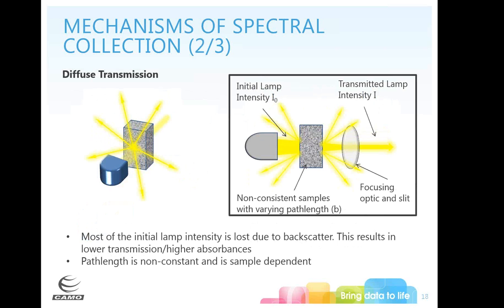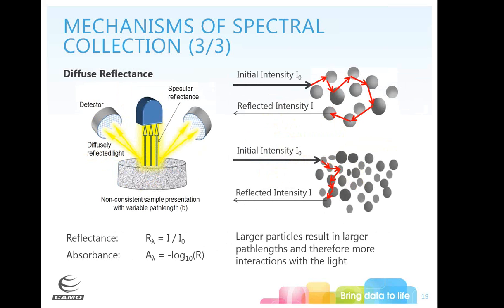A very common way to collect near IR data is diffuse reflectance, which is similar to diffuse transmission except you're collecting the backscatter. With diffuse reflectance, the light goes into your particles, bounces around, and some of it takes different path lengths and comes out. Larger particles have longer path lengths and therefore more interactions with the light, causing more scattering — larger particles scatter more than smaller particles, and these effects are wavelength dependent.